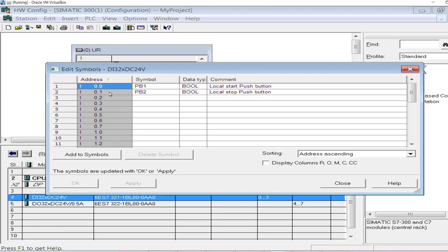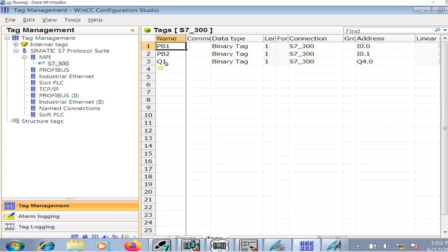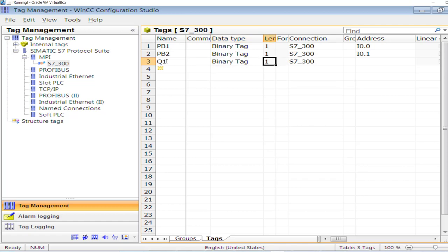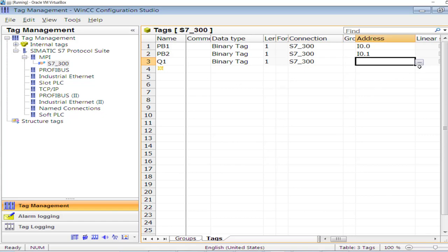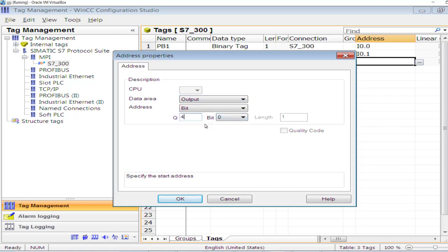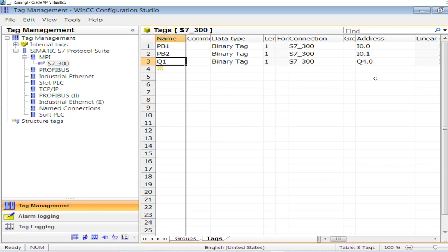I will be explaining the use of this a while later. Go to the tag management section — I have entered it. I will name it Q1, the data type is binary tag, the connection is S7-300 established under the MPI section, and the output channel address is Q4.0. The digital tag has been updated in the tag management database on WinCC.